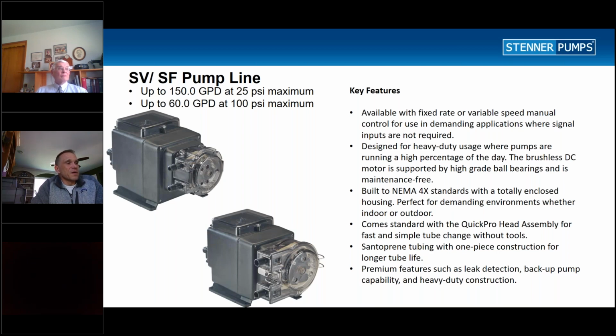But if you're in an area where the pump is being subjected to water in an outdoor application or is susceptible to corrosion, this pump would be ideal. What makes it so unique is that the NEMA 4X enclosure seals the motor. We have a better bearing set on this pump than we do on the classic pump. We can also change the tubes the same way as you would on a classic pump, with the cover. And the pump is also designed with a new leak detect feature. So if a tube does leak, you have the option to turn the pump off without fluid flowing all over the place.